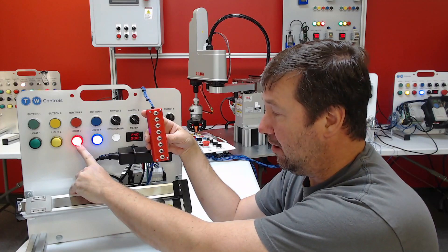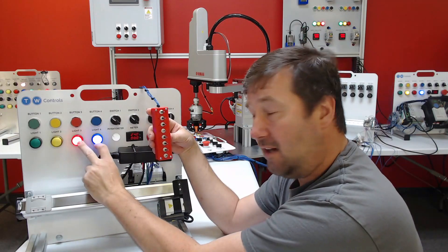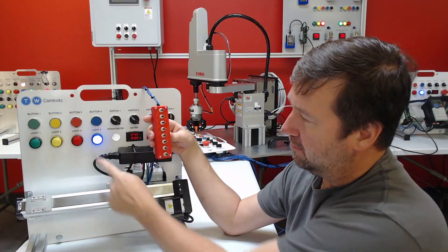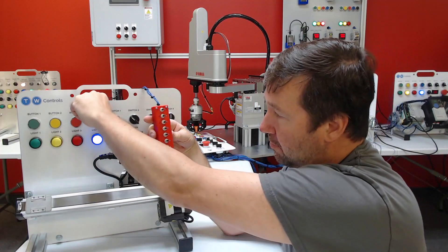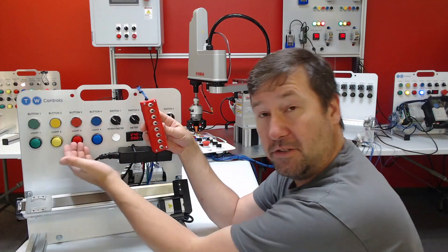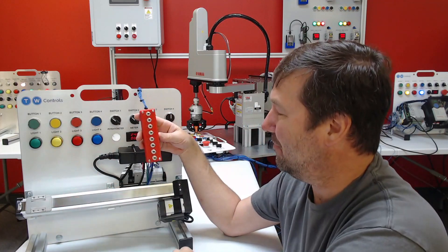Now if we had the high float, which was this one, make the alarm solid. And same thing both ways. You notice down here, we had our alarm buzzer. We press the silence. And it does silence the alarm. And notice we still flash our light. But our alarm buzzer is not coming back on.